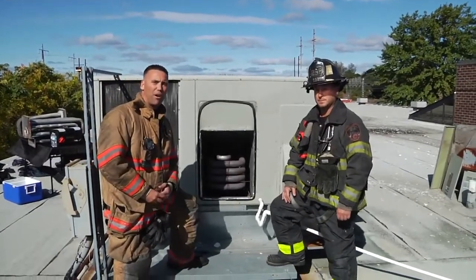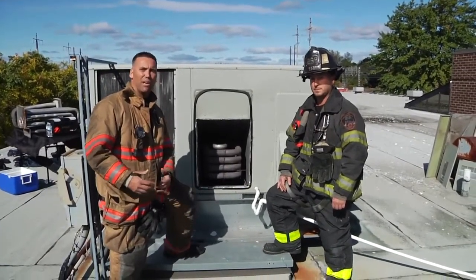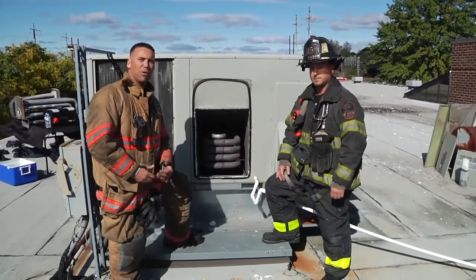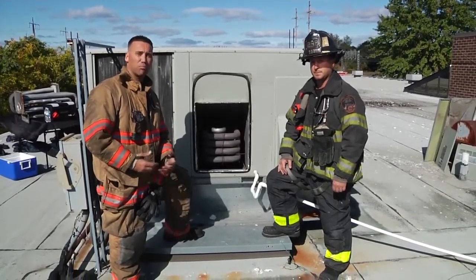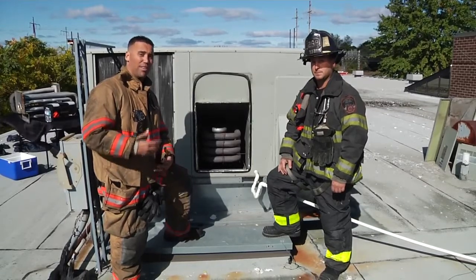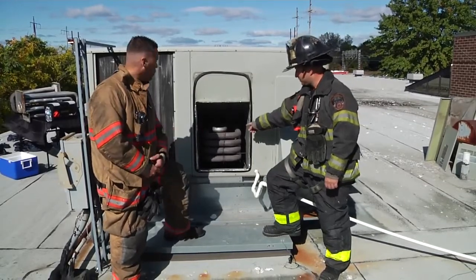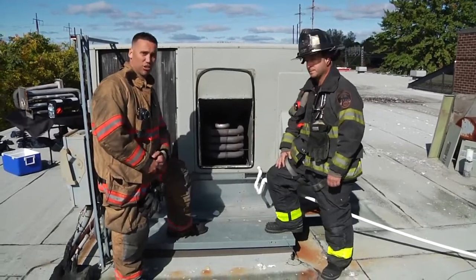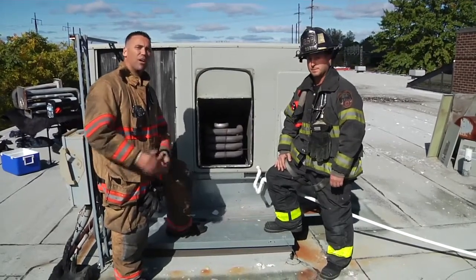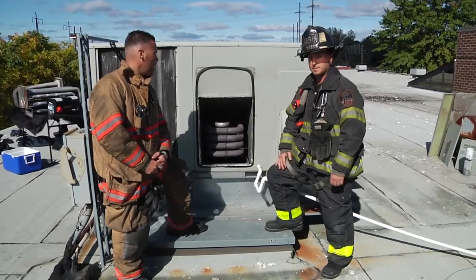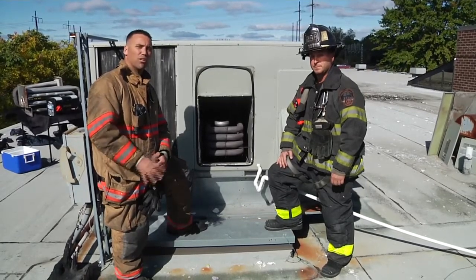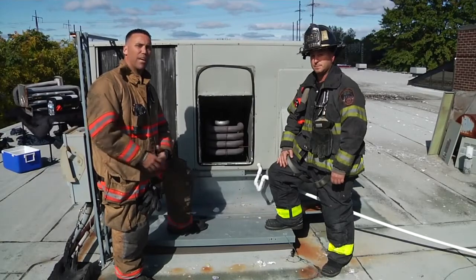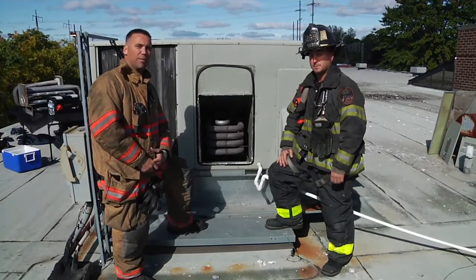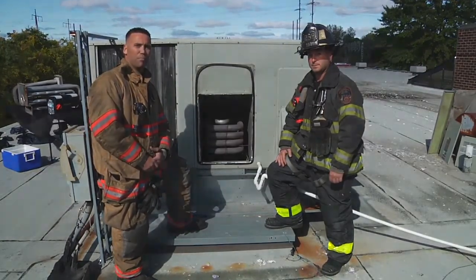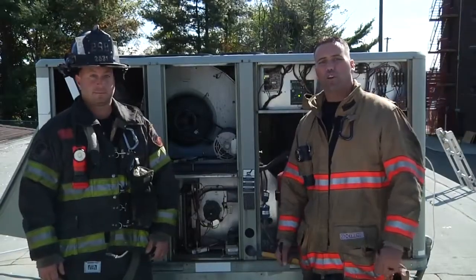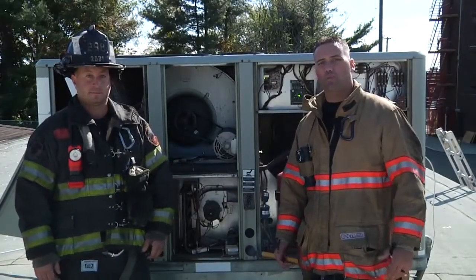So far, what we've been talking about is the air conditioning and cooling aspect of the RTU. When the building is calling for heat, it's going to start its burners, and the burner and the heat is going to enter these coils right here, and this is called a heat exchanger. You will see later on why knowing where the heat exchanger is and what it does is crucial to us investigating these units, because it can create an actual IDLH environment and be dangerous for the people operating inside of the building. I hope this was a good basic overview of the major components which make up a rooftop unit.